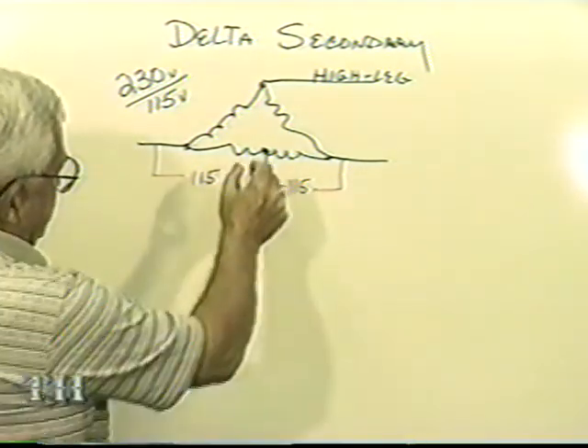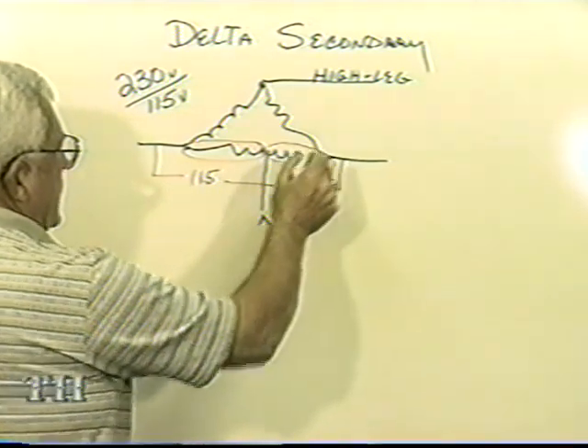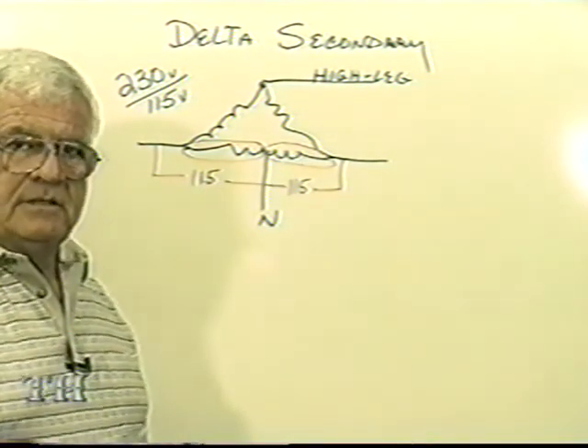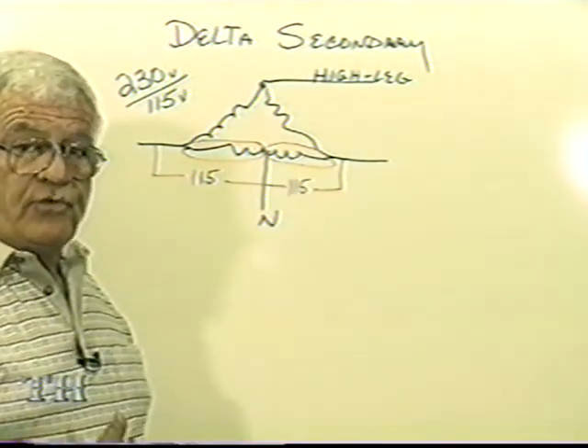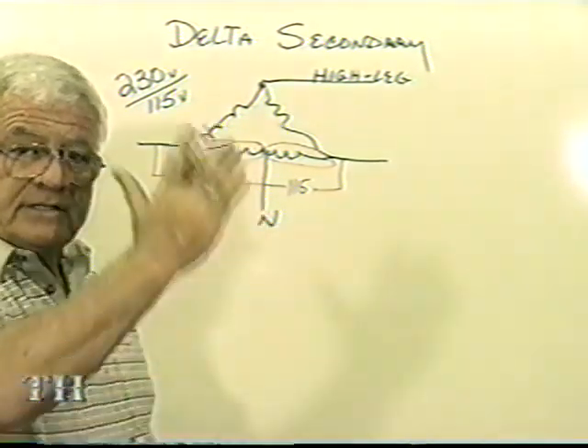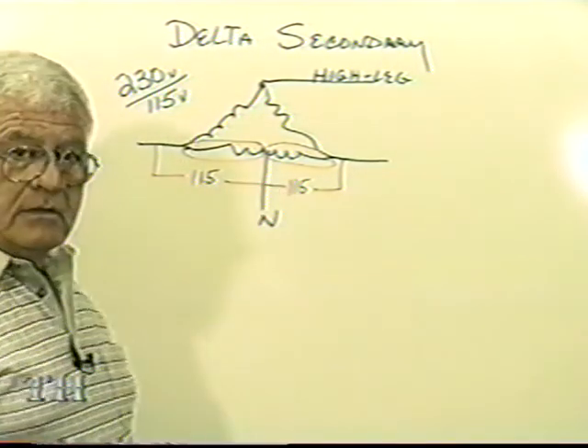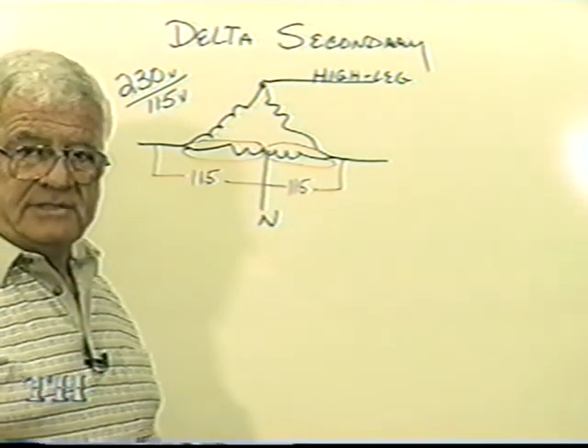Because what you're reading, this 115, you're reading what we call half of a phase. Your phase voltage is 230. The 115 is half of a phase. They take what they call a midpoint tap, a center tap.